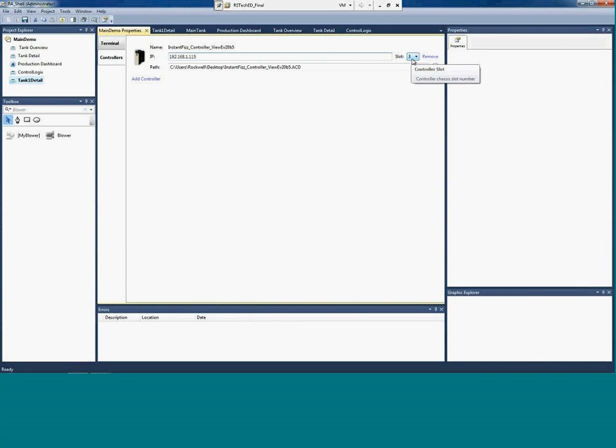And then the way the color animation will work at runtime, as Gordon will show you, is the list of ranges that I've configured evaluates from top to bottom at runtime, and when a value returns a true condition, the graphic will automatically update and show the colors that we defined for that particular state. If none of the values return a true value when we go through that, that's the purpose of this default state here, in that the object will return and use its default colors that were defined in the properties.